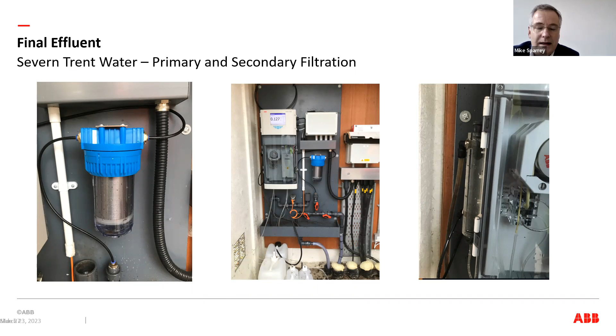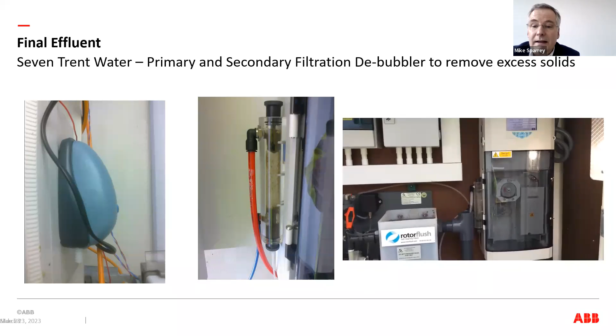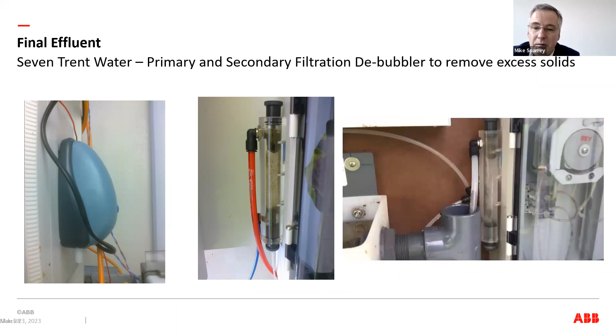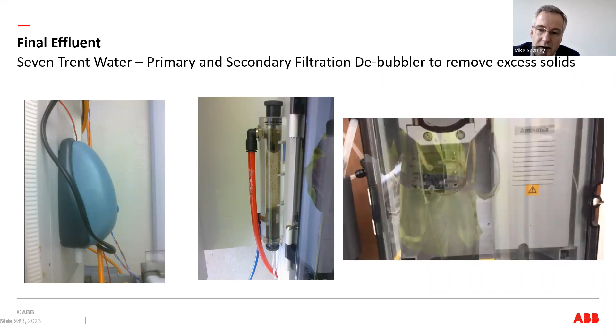The other thing we've done a lot of work on is a debubbler type system, as seen earlier in the presentation. This came from one of our service guys who modified the sample pot to allow the sample to flow through. We made some modifications on the inlet side, which let us bubble away any solids, making sure excess solids were taken out rather than passed into the monitor itself. You can see on the right a good area showing the solids being removed. We reduced that, and it certainly helped the instrument perform at its optimum.